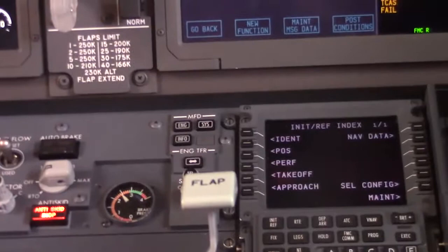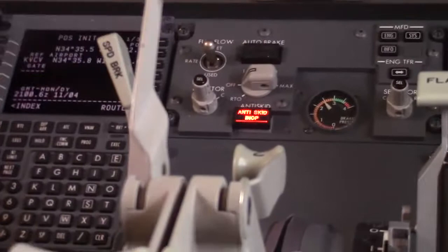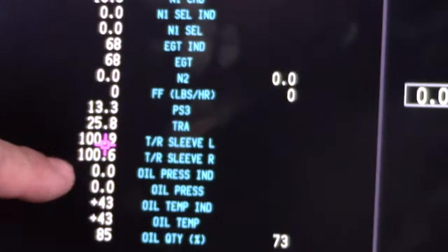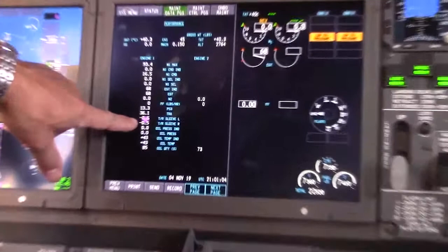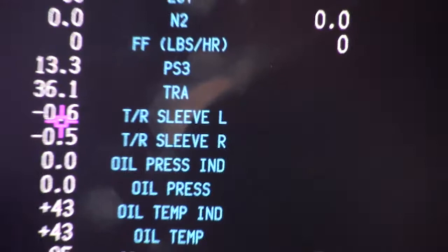Come back to this screen and we're going to hit the start function. So now we can deploy and stow the thrust reverser as needed. I'm going to come down here and deploy my number one thrust reverser. I'm watching my thrust reverser position open up to 100%. Once I've cycled it, now I want to close it so I can go ahead and stow it. I'm watching my thrust reverser close, and then at that point I can stop the function.